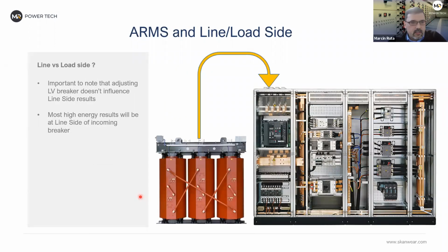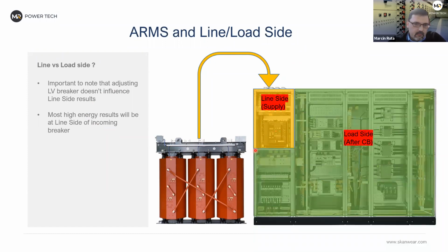And while we are here, I want to explain a little bit about the line and load side concept, because it's important when we talk about ARMS. ARMS will be implemented in the low voltage breaker. So everything we do with the low voltage breaker in this situation, whether it is setting adjustment or ARMS, will affect only the load side of the breaker, so everything behind the breaker. And everything we do with the medium voltage relay, which is installed upstream somewhere in the medium voltage switchgear, will affect the transformer, cable, and the line side, and actually the bus side also. So to put it in a graphic perspective, physically depending on how the switchgear is built, this will be the line side in our situation, and everything behind the breaker will be called the load side.